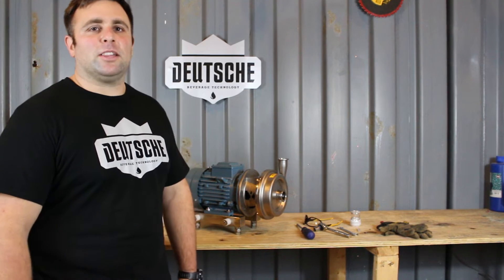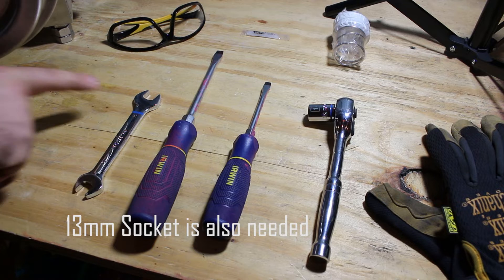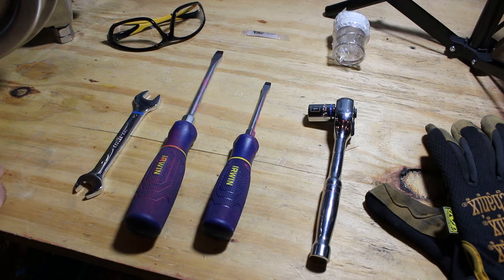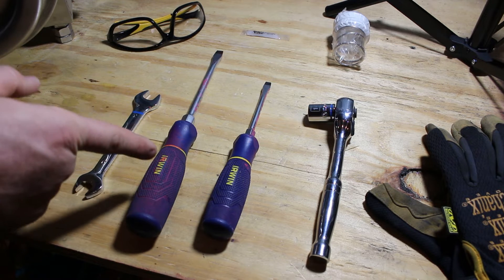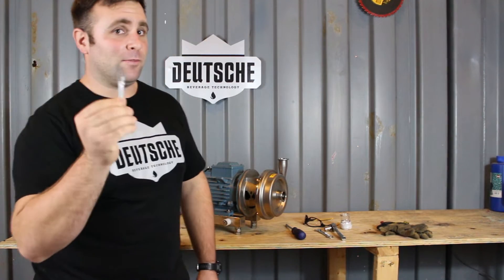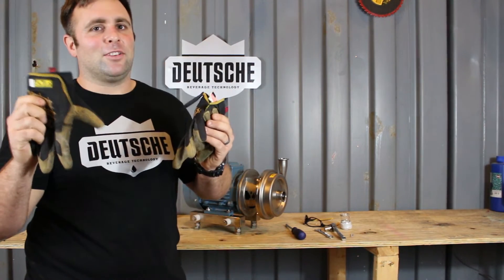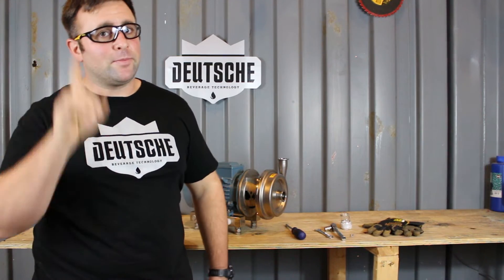Some tools and equipment that you're going to need to actually change the seal. For this specific model, a one and a half kilowatt model, you'll need a 13 millimeter wrench or ratchet. If you have a larger pump, you may need a 15 or 16 millimeter wrench or ratchet. You'll need two screwdrivers — a large one to lock the shaft and a small one to help remove the pump seals. Your pump seal kit. Some food grade grease to lube things up real nice. Some safety gloves — got to protect the money makers. And of course, let's all remember safety first.